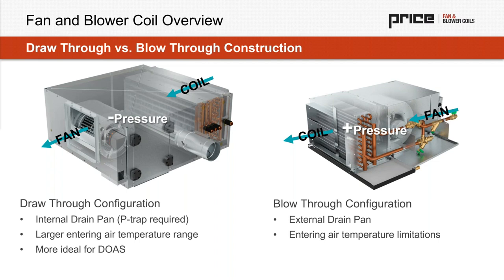So a draw-through product, like we see on the left, is a negatively pressurized casing. That means we're going to need a fully internal drain pan. We're going to need to provide a P-trap on that drain pan. We need to overcome the internal static pressure drop with hydrostatic pressure in order to properly manage condensate. On the right, the positively pressurized fan coil is going to have drain slots in the bottom of the coil section, and the nature of the product is it needs some leakage out of those coils because it needs fluid to be able to drain through it.